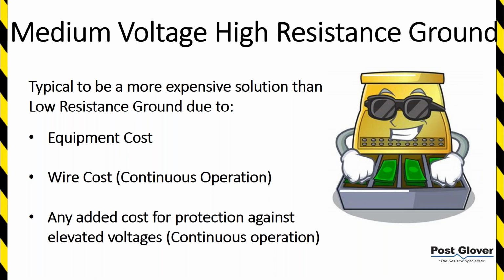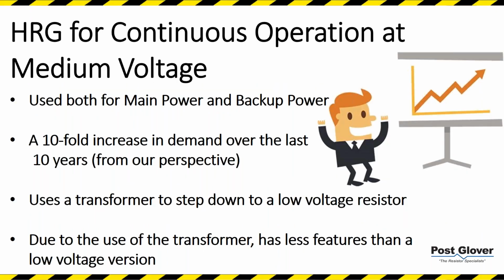But usually, whereas in low voltage there are a few different reasons to use high resistance ground, you do have the continuity of service, the continuation on a fault. You have arc flash reduction, severe arc flash reduction, so much so that they say at a line to ground fault there is no arc flash. There is potential there. I would say that gets limited down to just equipment protection and continuous operation for medium voltage, because we don't really see as much arc flash reduction at medium voltage. But you have your reason. The processes nowadays are a lot more expensive, and downtime is just a lot more expensive.